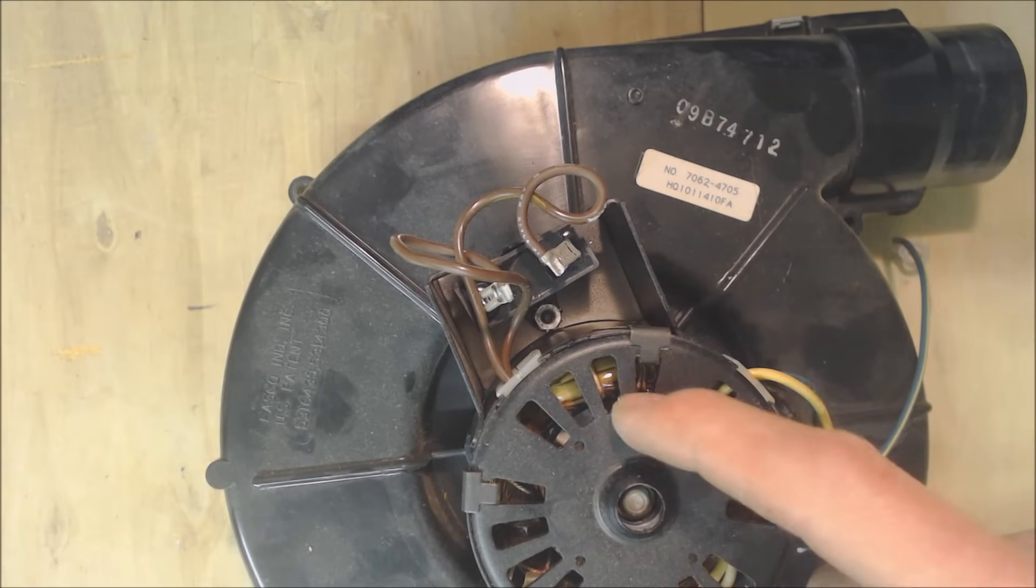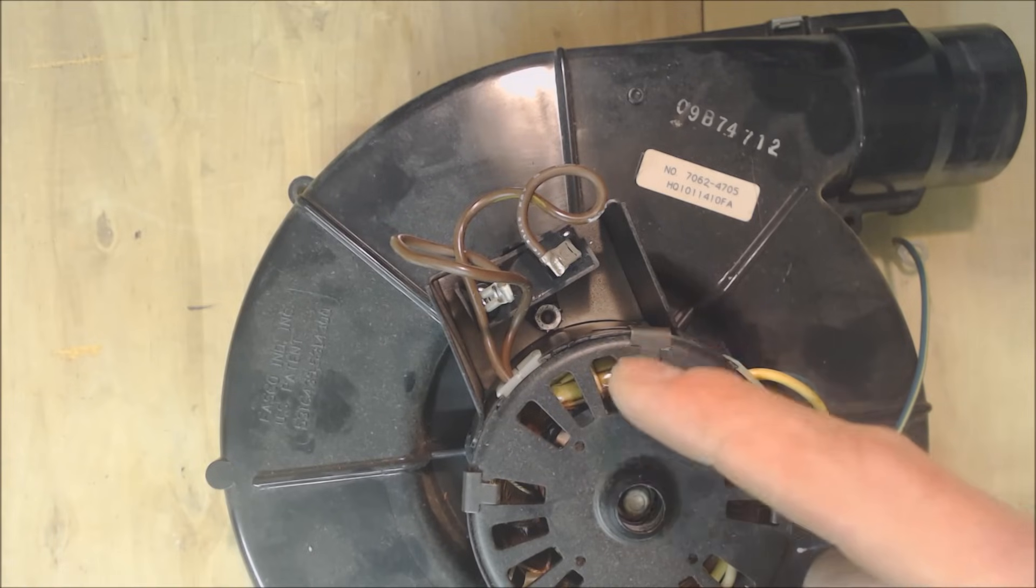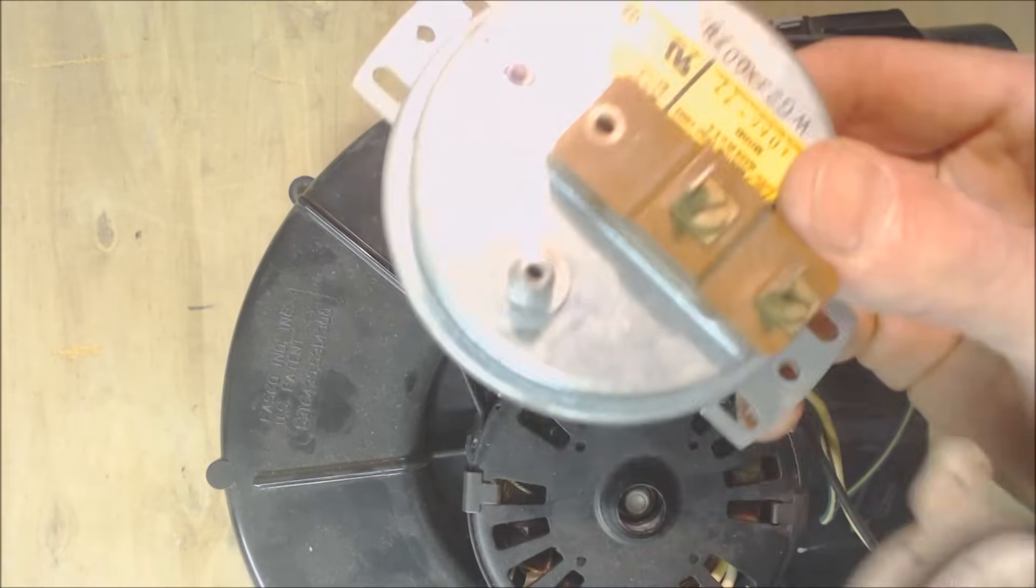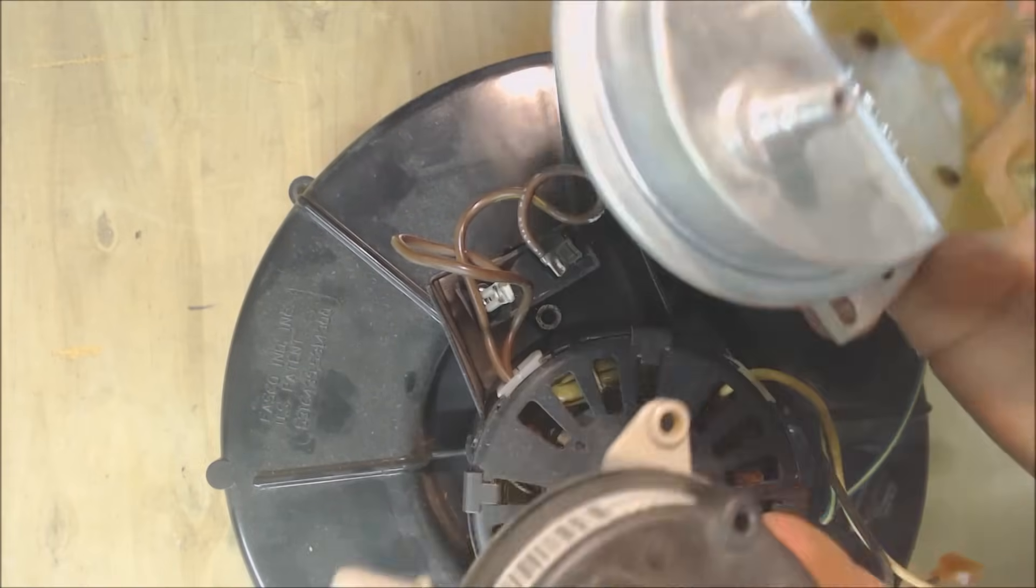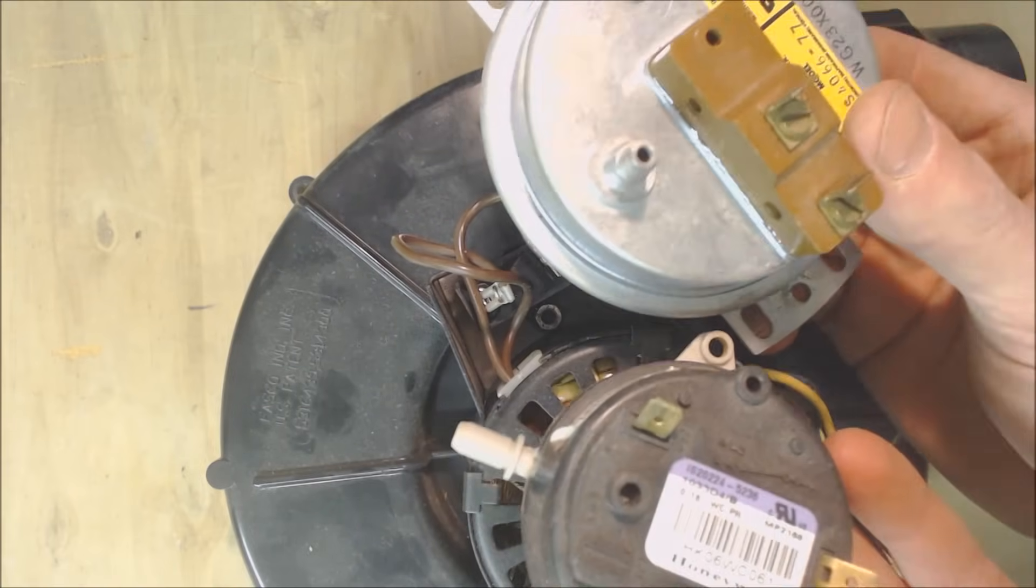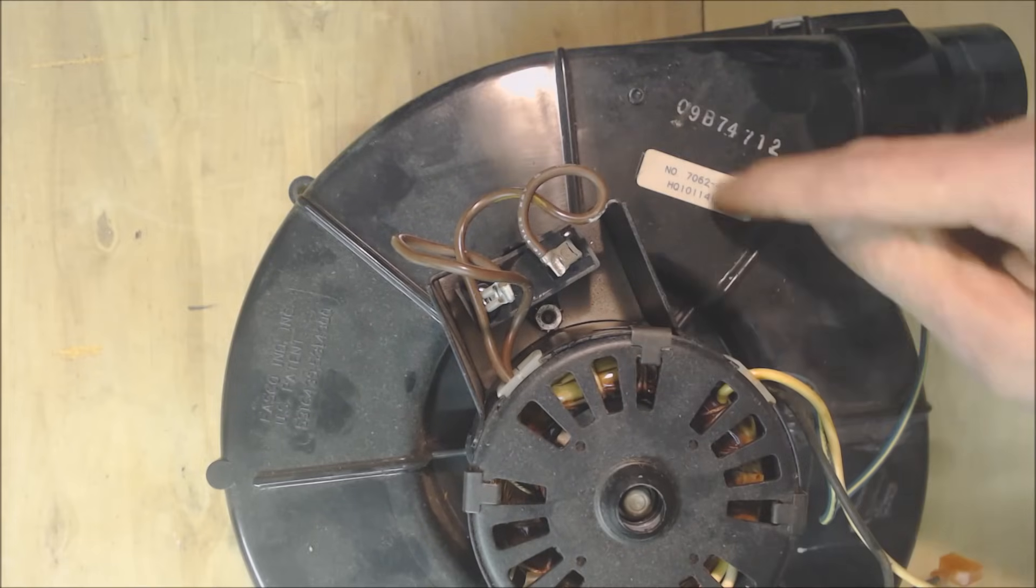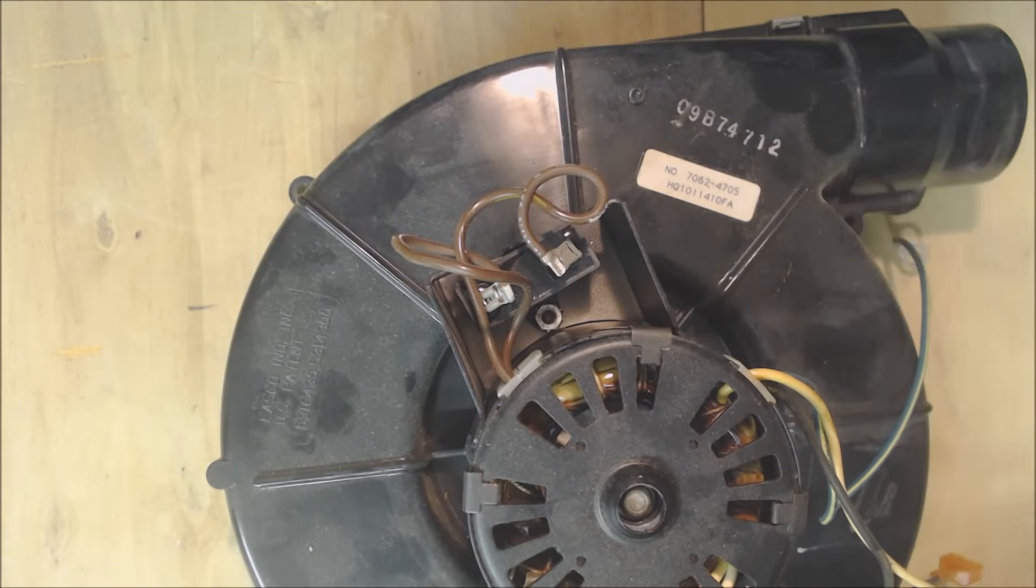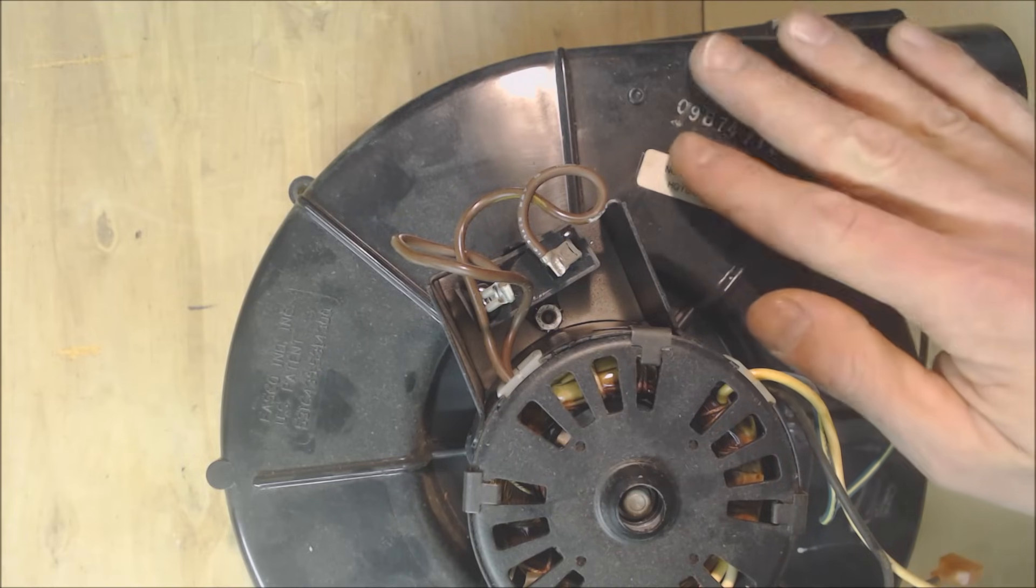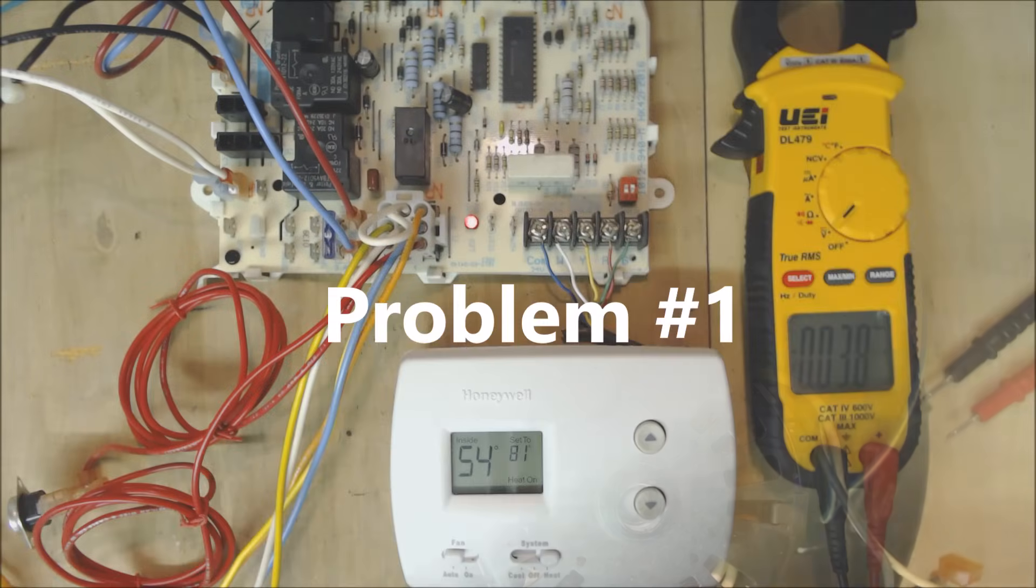So this needs to turn on first and then it's proven by a pressure switch. A pressure switch could look something like this or like this, but basically they are sensing the negative pressure coming from either the inducer motor housing or through a condensate drain in order to determine that this is actually working and that there's no clogs.